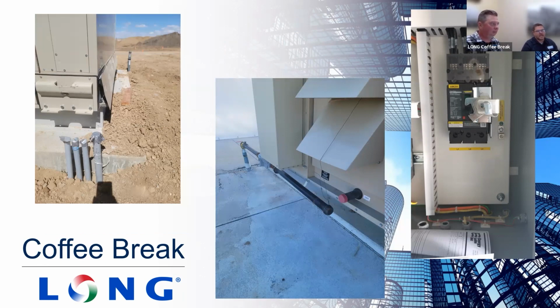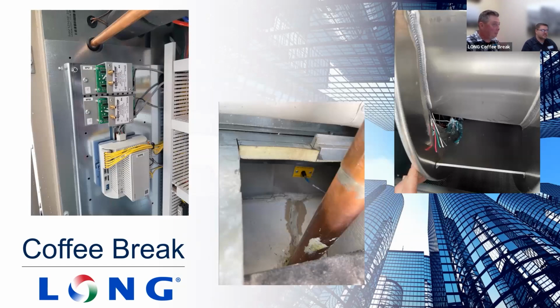We have another here with gas line not connected, so we can't verify gas operation or pressure. It's literally hanging there from a string and under a pressure test still with a pipe cap on it. Of course, line voltage not connected to a disconnect. This is an example of the controls not quite complete on the left there. In that instance, if the temperature controls contractor has the wire in the unit and it's coiled up and landed and labeled, we have absolutely no issue with landing those controls and assisting with that to move the project along. But if it's not there at all, it's kind of hard to commission the unit or even start it for that matter.